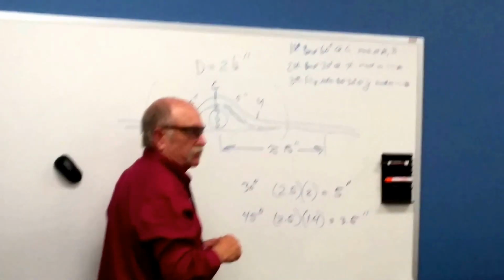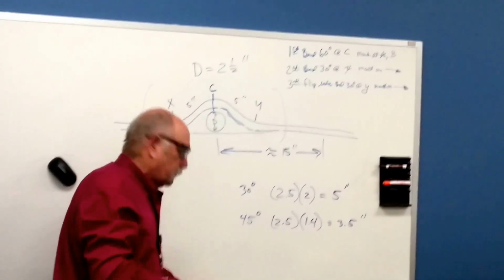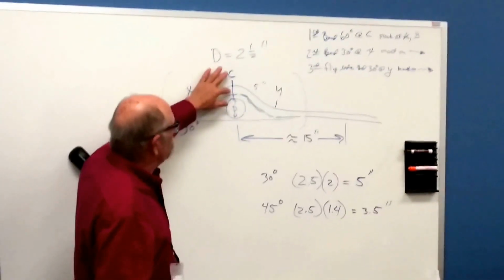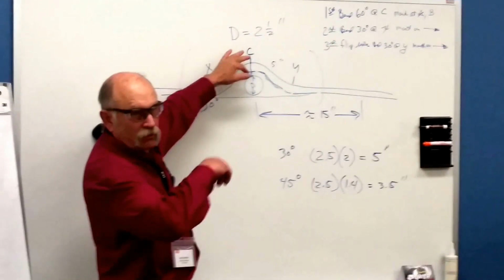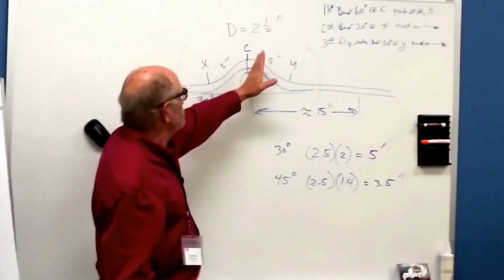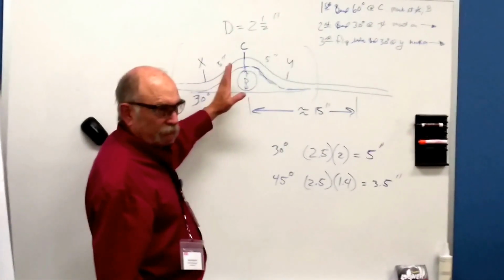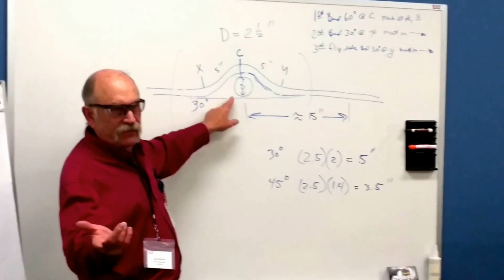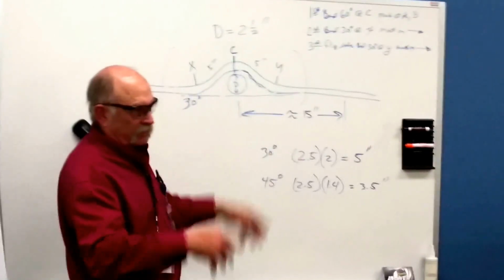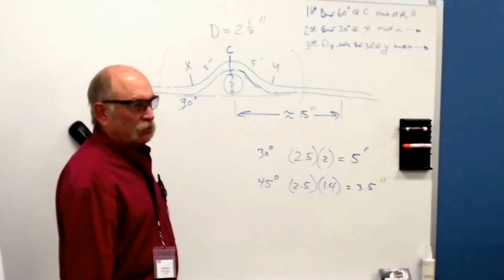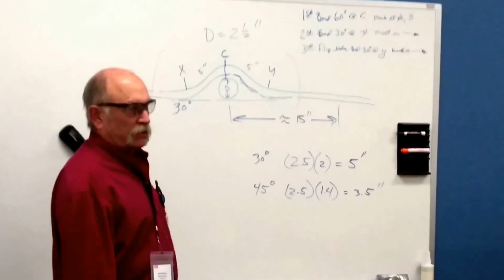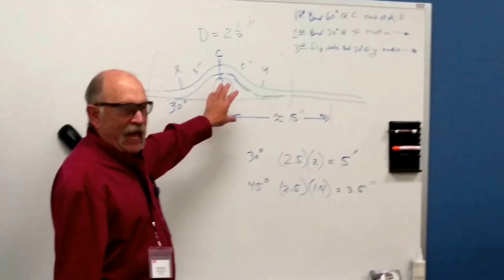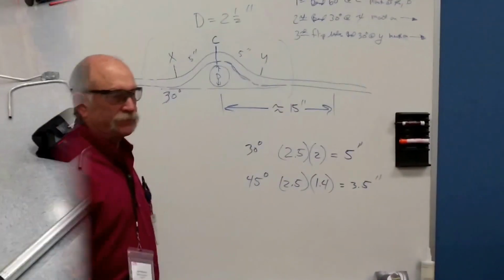Okay, so that's critical, and the critical thing here, I always had trouble with people bending these saddles. They'll put the C on the arrow also. If you put the C on the arrow, you're going to be offset. Okay, so this should work real well. I tried it out with a 1/2 inch. I made one bend and it came out fine. So your first bend should come out perfect. Okay, so try a 3/4, try a 1/2, try the different bend rates.